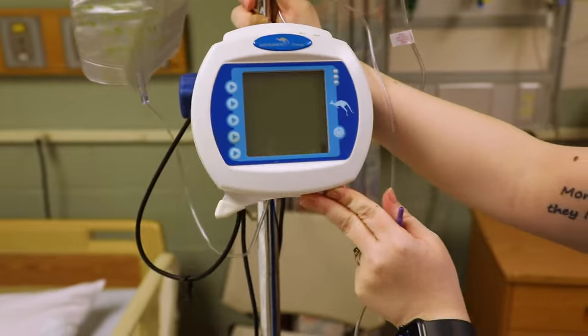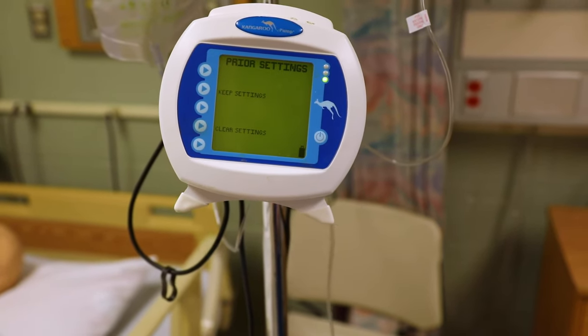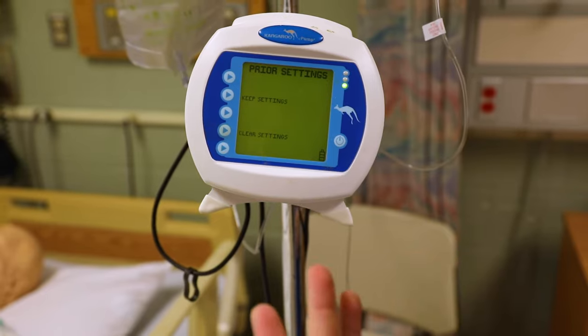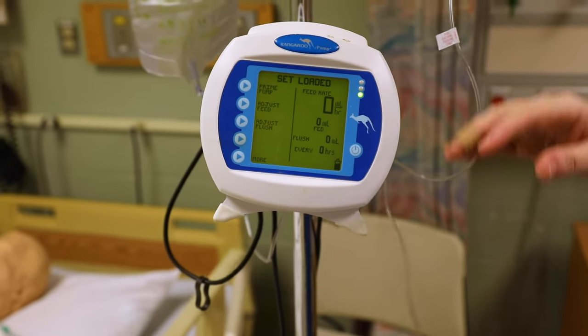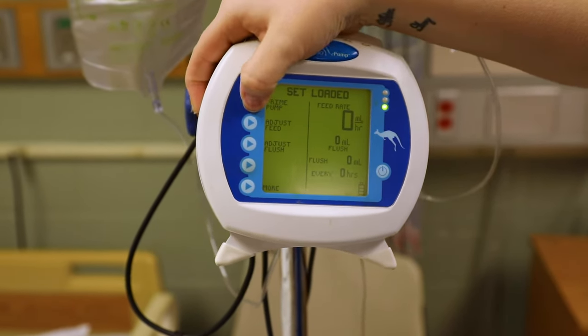Go back to the front — that's your power button. You can keep your settings if you're using this on the same patient again, but for this demonstration we're going to clear our settings. There's an option that says 'Prime Pump' — just click that arrow.